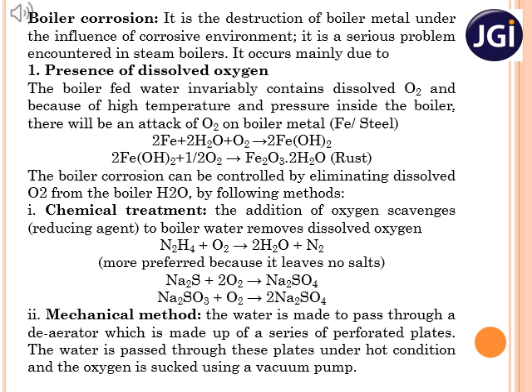The second reason for boiler corrosion is presence of carbon dioxide gas in the boiler feed water. Also, whenever bicarbonates are decomposed, they liberate carbon dioxide gas. Dissolved carbon dioxide produces carbonic acid. This carbonic acid attacks boiler metal and hence there will be boiler corrosion. The dissolved carbon dioxide can be easily removed by adding a base like ammonia. Added ammonia neutralizes carbonic acid and hence corrosion may be avoided.